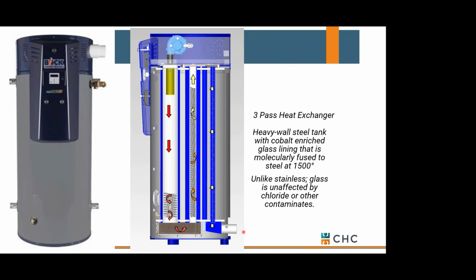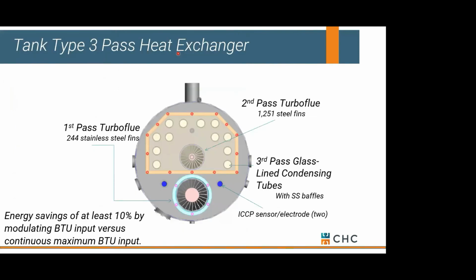Now, this is typical of most tank type water heaters. They're trying to get as much heat as they can out of this product of combustion. And if you look down at the top here, here's the first pass where flue gas is sending down towards the ground, second pass where it rises up, and then third pass where it gets equally distributed through all these additional surface area before it physically vents the water heater. And all that's surrounded by a jacket of water, trying to pick up as much heat as we can as we're firing that natural gas.